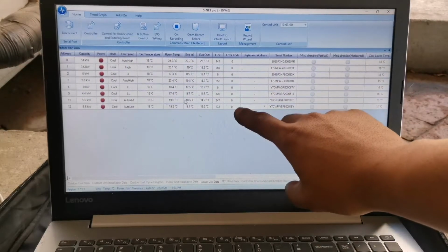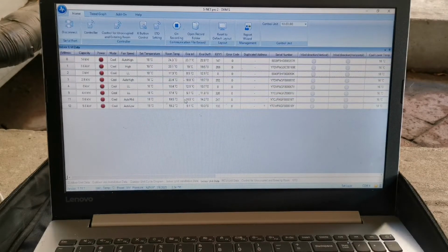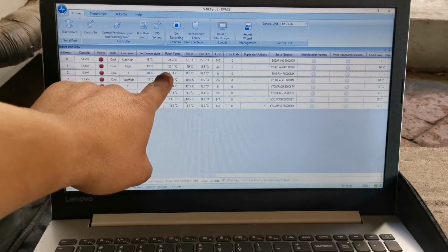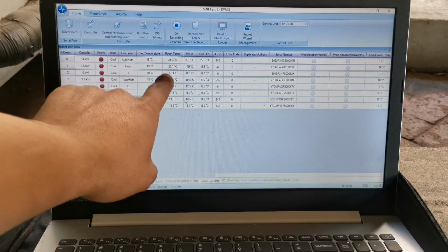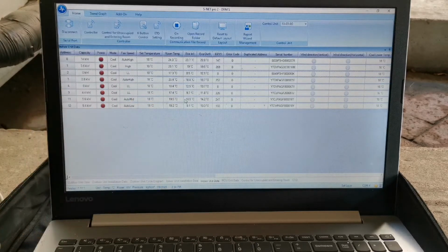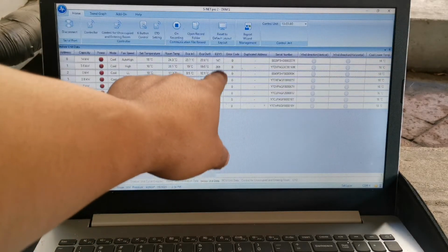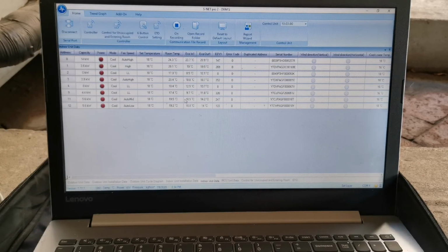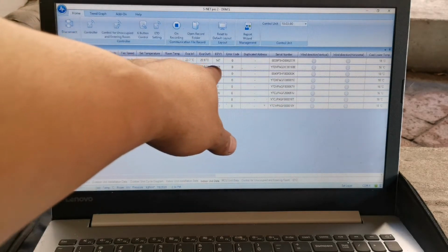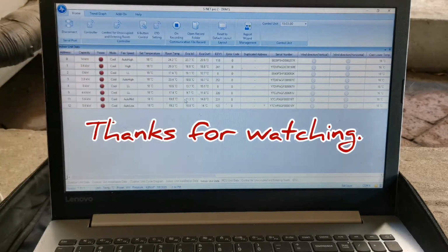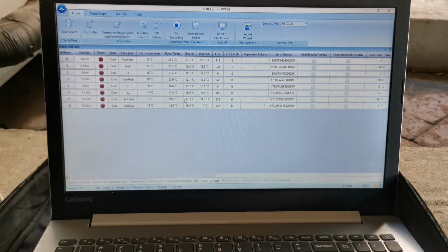This is basically why our suction pressure and high pressure drops so quickly, because we're satisfied. Our room temps are all within 1 or 2 degrees from our set point. So all of these units, all the expansion valves, they basically closed up and they're starting to open up again. So let's have a look and see. But still, there isn't a big difference on those first units there, and that room temperature is still at 24.2. That one is still at 20.3. So there's nothing happening on that evaporator coils.